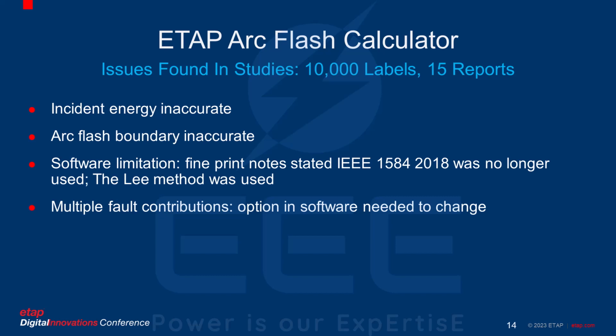There were also more buses with different issues that we won't address in this video. On this issue, the report had a fine print note telling them they may have issues because of the dimension of the enclosures and the gap. Now, the dimension and enclosure and the gap were correct. It came from the manufacturer and the drawings matched. However, the software had limitations.